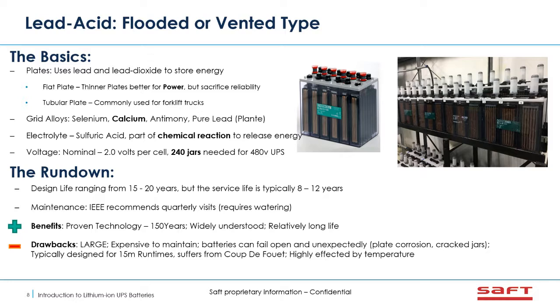It's part of the chemical equation to release energy out. The voltage of this battery is 2 volts per cell. So commonly we have 240 jars to make up the 480 volts UPS. Most importantly, the rundown here, these batteries have a design life ranging from 15 to 20 years, but we typically see the service life of around 8 to 12 years. Maintenance, these are pretty high maintenance. They do require topping up, and IEEE recommends quarterly visits to the battery.